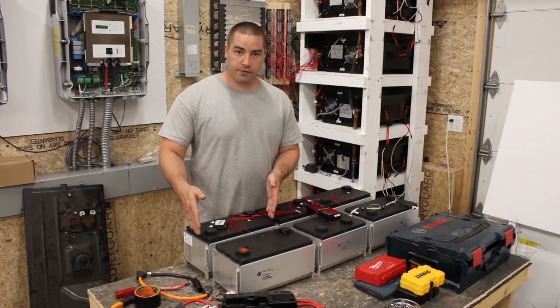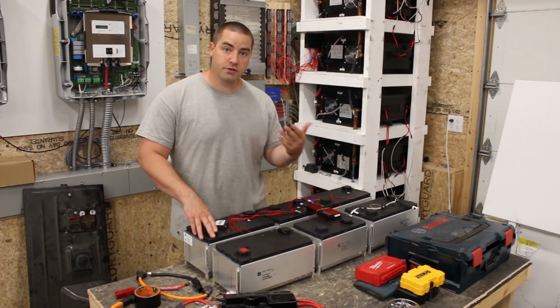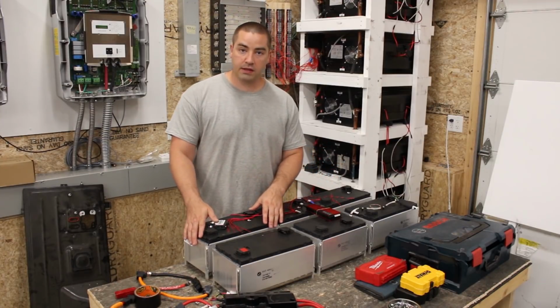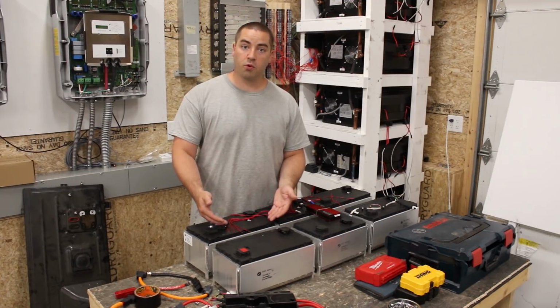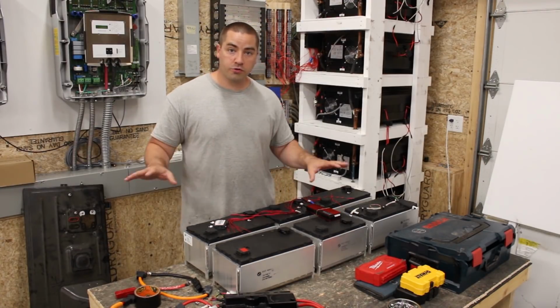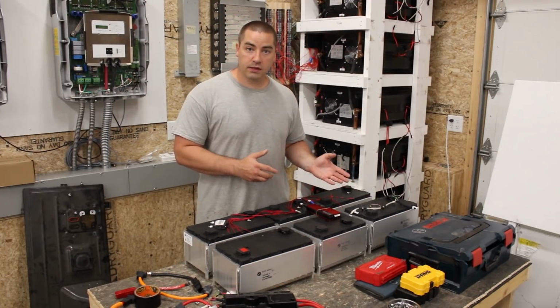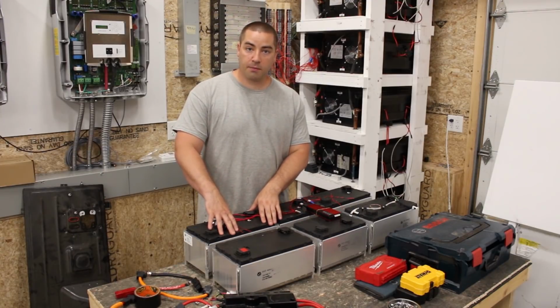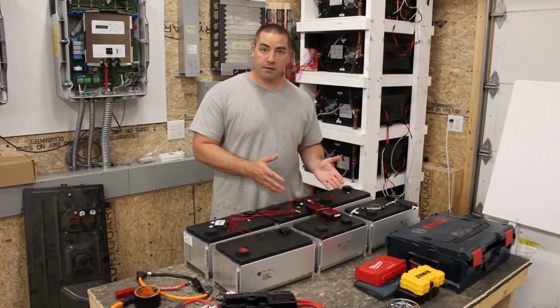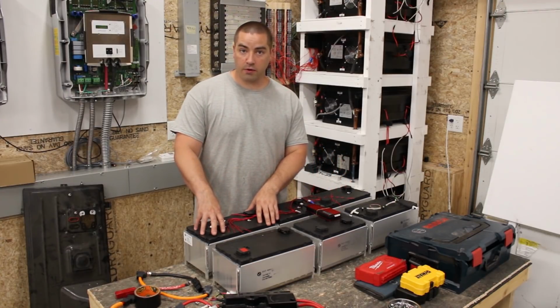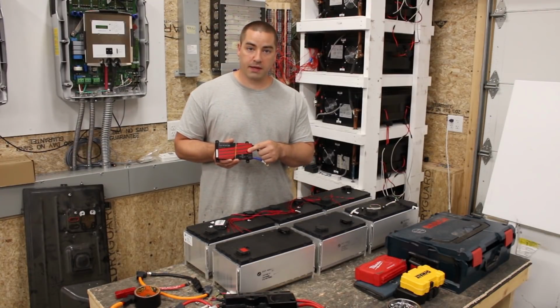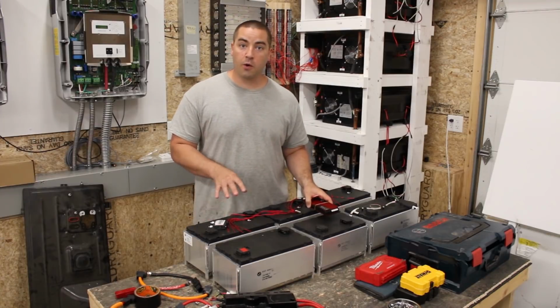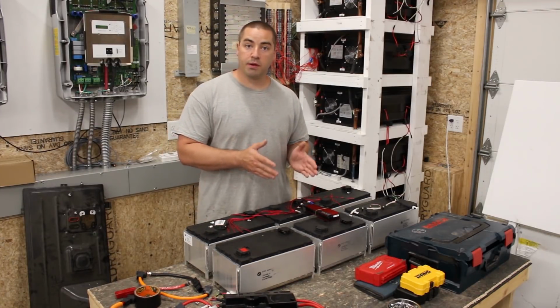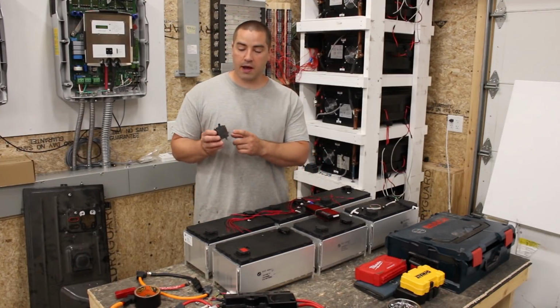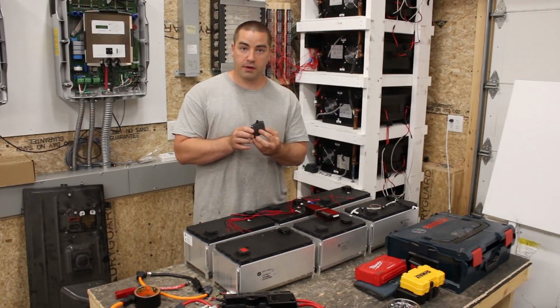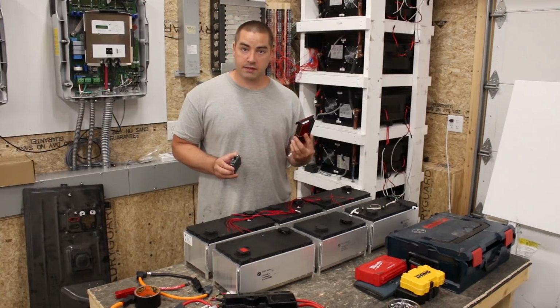There's a limiting factor of how many amps a cell can take, but there's also the limiting factor of thermal. The cell gets hotter the more amps it's charged with or discharging. If you want to play it safe, go with the weakest link. These are 90 amp hour cells, so I like to pick a BMS close to that rating, in this case a 100 amp BMS. For circuit protection, go half of that rating, so 45 amps, and the closest I can buy is a 50 amp breaker. So I could get a 50 amp MidNite Solar breaker with a 100 amp BMS.